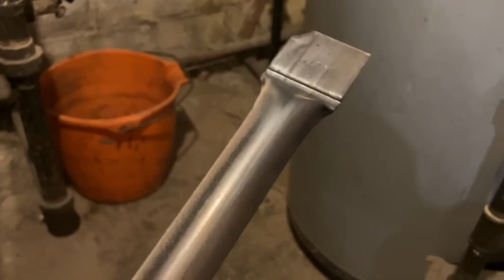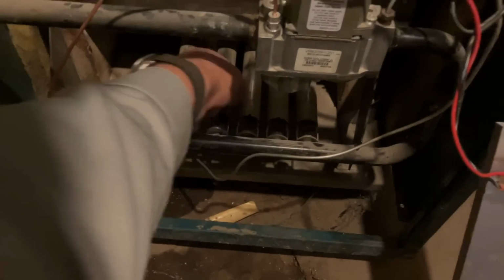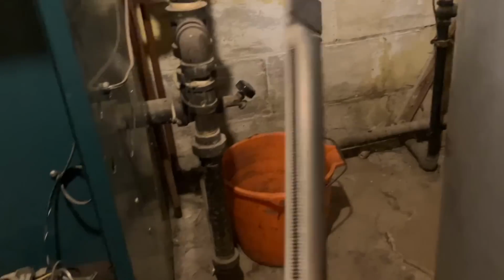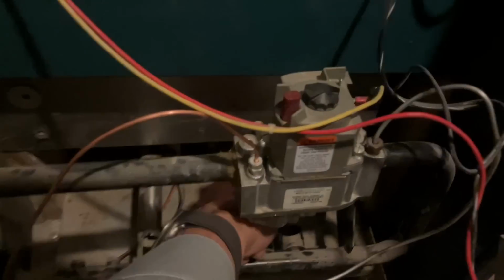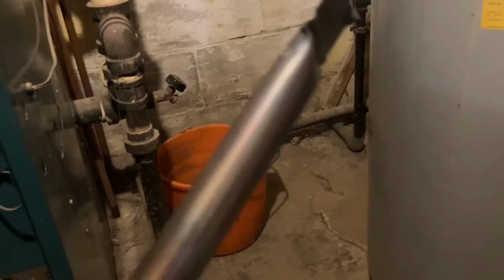Remove this front plate, which can be very hot if the boiler just ran, which it kind of did, but my hands are numb to that stuff. Let's take these burners out. Okay, perfect. You want to see if there's any rust on here. That means you got some water or moisture in the combustion chamber, which is usually indicative of the start of a leak on the heat exchanger. I'm banging these as I inspect them one by one, getting all the dirt and dust out. That little click you just heard was the solenoid valve on the gas control valve closing because the pilot was extinguished when I turned off the gas at the gas cock.